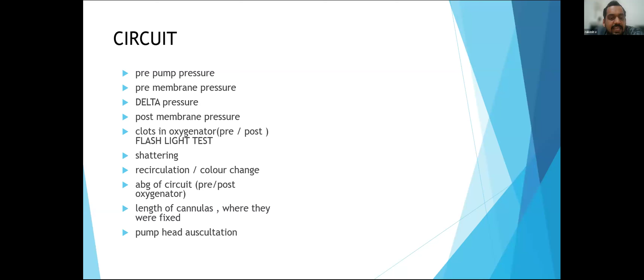So if you're a good physician at the bedside, just like auscultating the heart sounds and the breath sounds, you need to auscultate the pump head of the ECMO also. In case of a bearing failure, or a clot that is causing obstruction to the bearings, there will be a gurgling sound that will be a new or adventitious sound compared to the previous day. So you need to auscultate the pump head on a daily basis to identify the complications earlier.